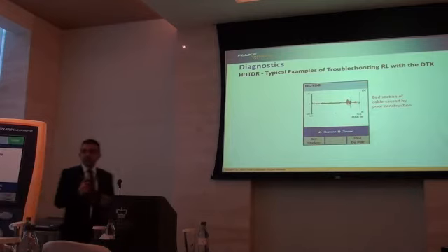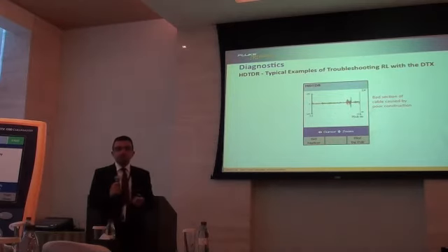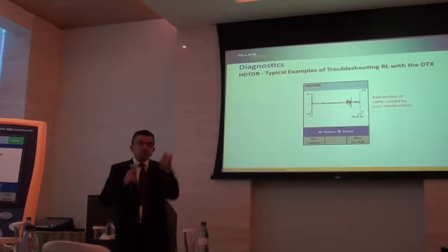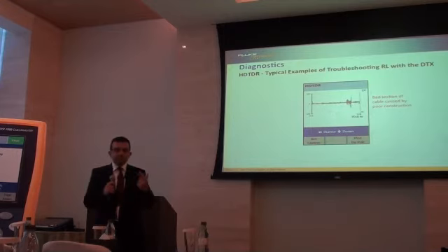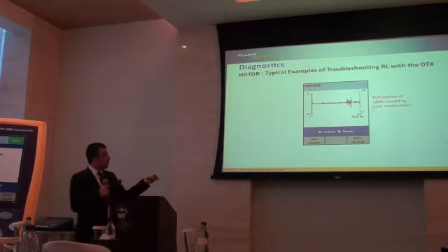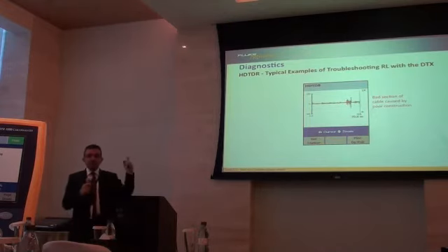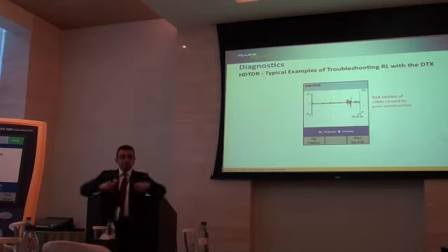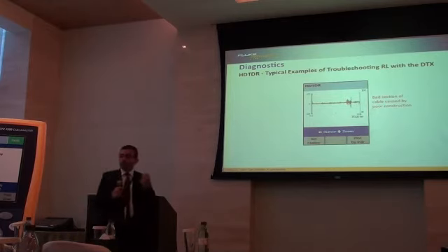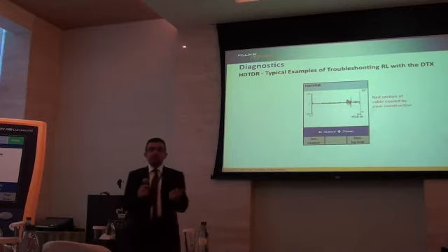How can it be bad? Probably installation, probably something wrong in the manufacturing of the cable. It can happen. So from here you can know where your problem is, and then you can go to 70 meters of the cable to see what is happening. Maybe an excess bend, maybe a heavy bend on the cable, so you can try to analyze the root cause of the problem.